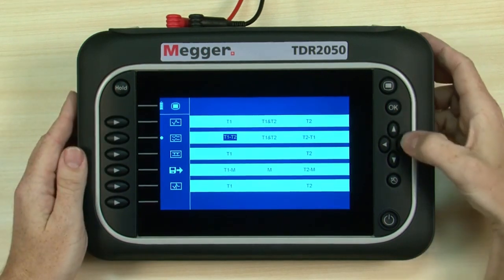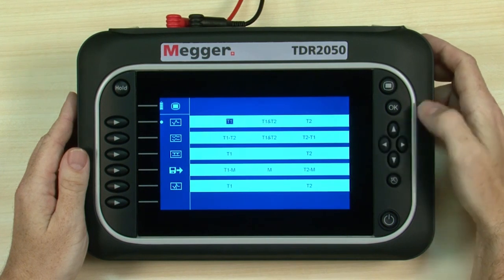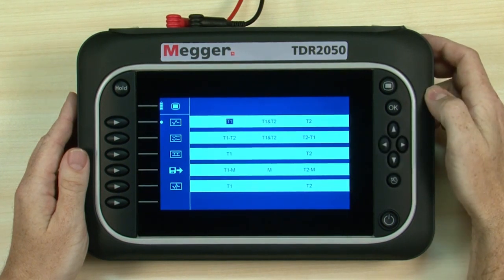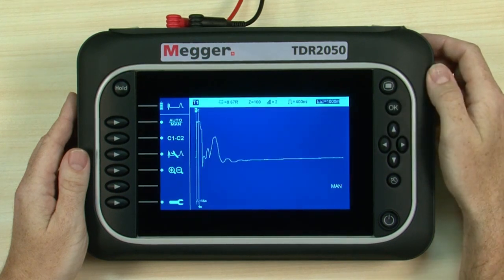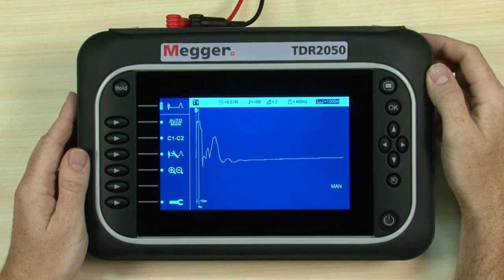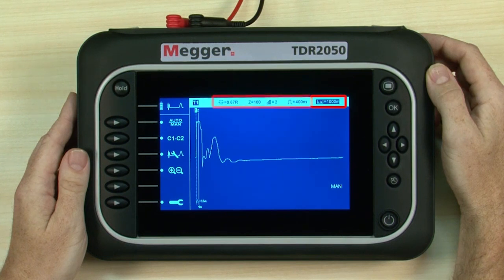Using the navigation buttons to navigate left, right, up and down, we highlight T1 from the full screen trace mode section. The OK button is used to select the highlighted action or to accept entered text or information. There is an event to examine on the live trace towards the near end, but we need to select a more suitable range for our cable. Range is immediately changeable, while the other settings can be altered using the relevant selection.